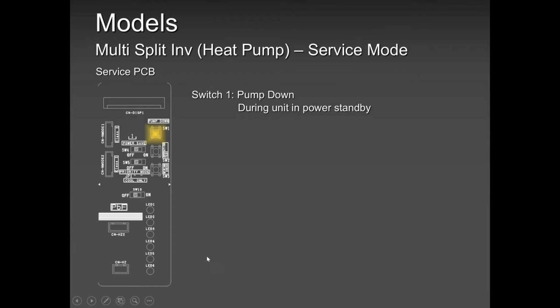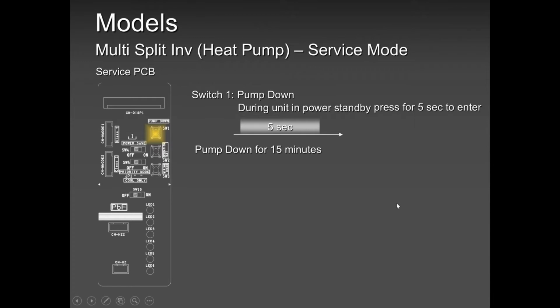So when you pump down the system, you close the liquid line, then you press and hold that switch, SW1, okay? The unit will go into pump down. You press and hold for 5 seconds, the unit will start, and when the compressor starts, each and every unit goes into cool mode, the electronic expansion valve is fully open, all the gas is collected to the compressor, and the compressor is expected to run a maximum of 15 minutes. I have never seen 15 minutes, even on big jobs, but you never know. Mostly 5, 7 minutes, and eventually it will shut down.